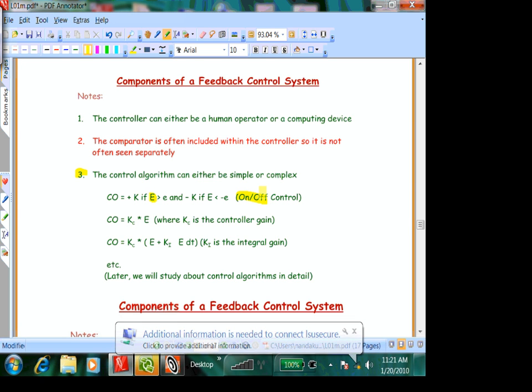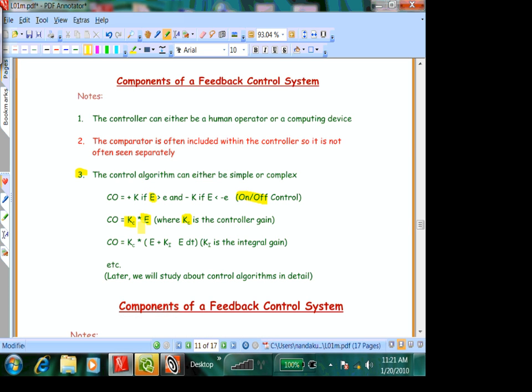The more sophisticated control would be one where you say the controller output is proportional to the error. Kc is called the proportional constant. Okay? So if the error is 2%, then the controller action will be calculated based on that. Of course, as a designer, you are supposed to tune the controller constant. What should that be? This is called the gain. So for 1% error, how much fuel should I burn? For 2% error, how much fuel should I burn? You need to figure that out. Once you have the model, you'll be able to figure that out.